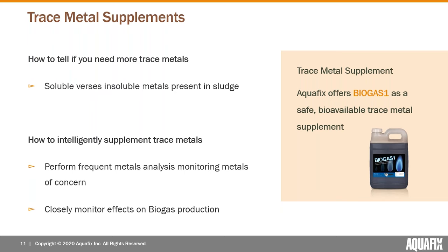For metals analysis, look for soluble versus insoluble metals — you can use a centrifuge to remove heavier solids and analyze the supernatant. Influent loading measurements are always important; monitor COD, nitrogen, and phosphorus for fluctuation. If possible, communicate with upstream high-COD sources to level out their flow. Occasional nitrogen or phosphorus deficiency can usually be efficiently supplemented.